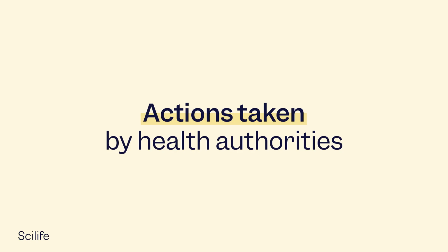After the investigation is completed, the organization should offer a response to the complainant, either the customer or regulatory authorities. Any decision or action taken that is relevant to the complainant should be communicated. If the product is on the market and/or if it can impact public health, you must report the information to the appropriate regulatory authorities as soon as possible. If the complaint cannot be immediately resolved, then you must still propose a solution.